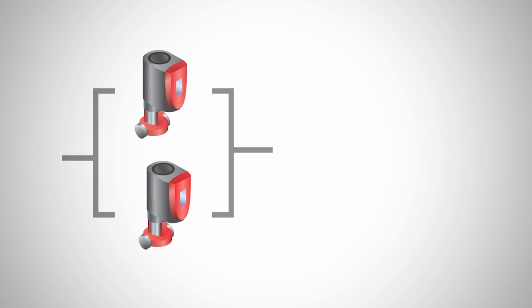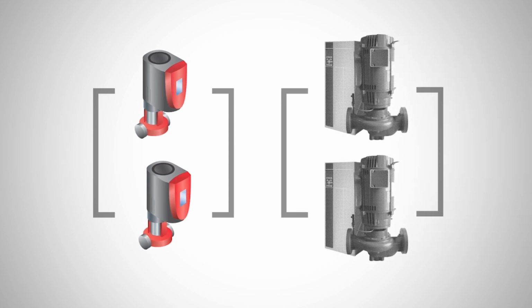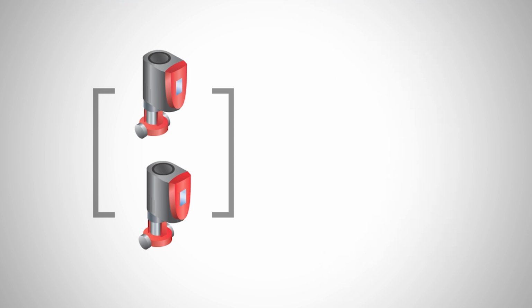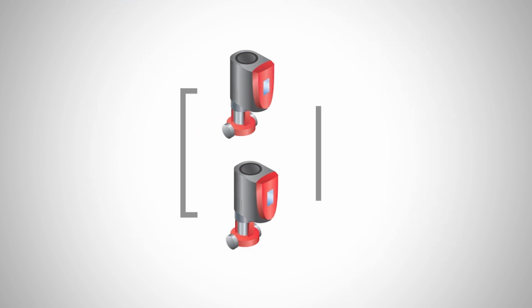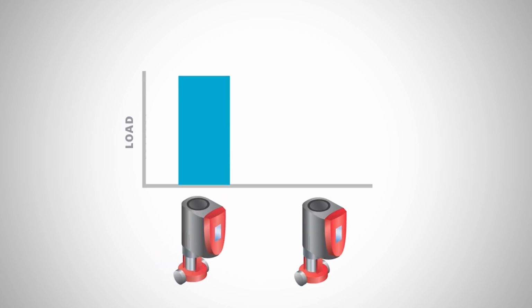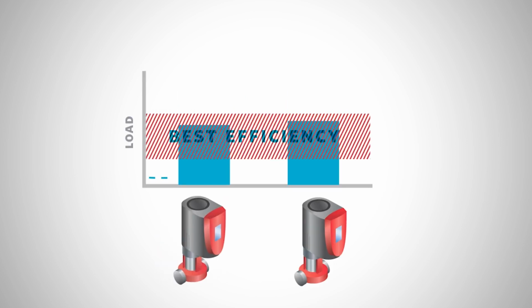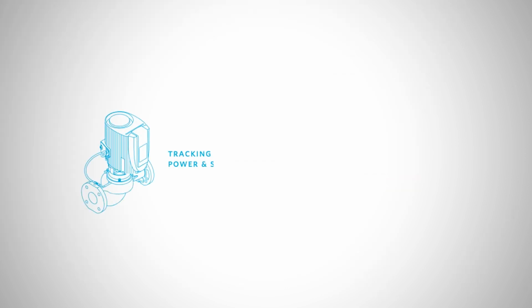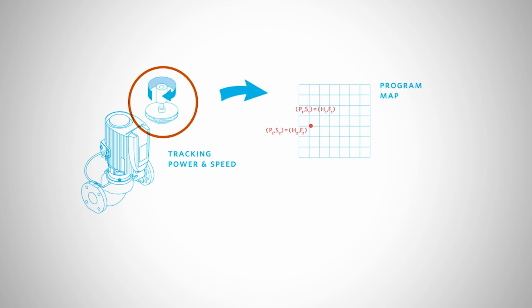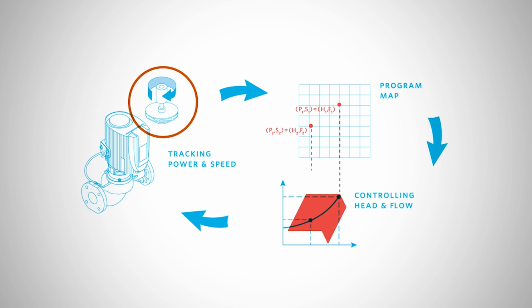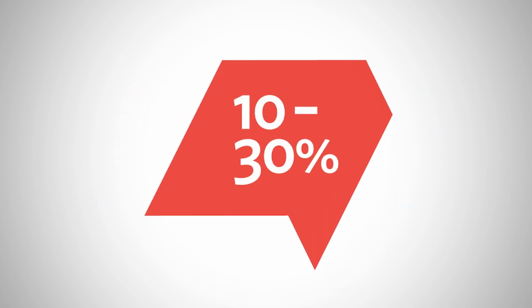Multiple smaller pumps, configured in parallel, are less expensive than fewer, larger pumps and circulators installed in the traditional duty standby configuration. Even more important, pumps installed in parallel can be staged and controlled for best efficiency across the entire pump array. Armstrong Parallel Sensorless Pump Control is an algorithm embedded in the pump controller that stages multiple pumps on and off and regulates pump speed based on best efficiency. This control approach saves an additional 10 to 30% in operating costs.